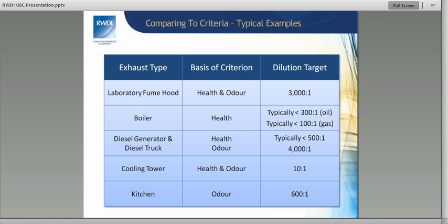The atmosphere has to dilute that with an extra volume of clean air to get to that 2 to 1 ratio. So if we have 400,000 CFM of plume, you have to dump in another 400,000 CFM of clean air. The atmosphere has to do that work to get it diluted by that extra factor, so it does become difficult.